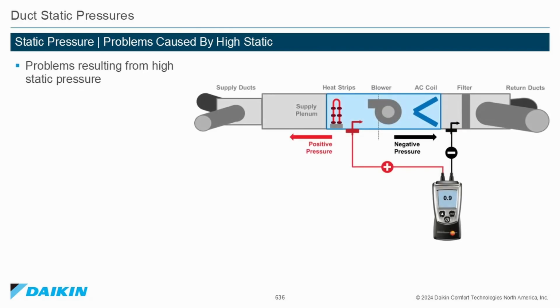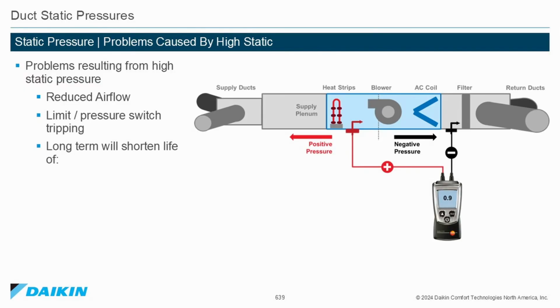Problems caused by high static pressure. Problems resulting from high static pressure: reduced airflow, limit or pressure switch tripping. Long term will shorten the life of the compressor, heat exchanger, motors, and components.